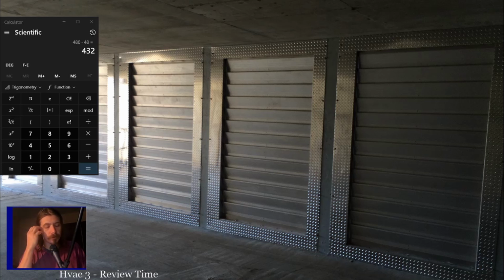4.4, control circuits and low voltage power sources, talks about isolating a faulty circuit using the process of elimination. So you try to narrow it down: make sure this thing's okay, this thing's okay, this thing's okay, eliminating everything you can until you get down to the faulty component. As you narrow down where you're at, you want to isolate that component and check it. A good example, something you should be doing all the time, is isolating a faulty circuit component and verifying that that's the issue.